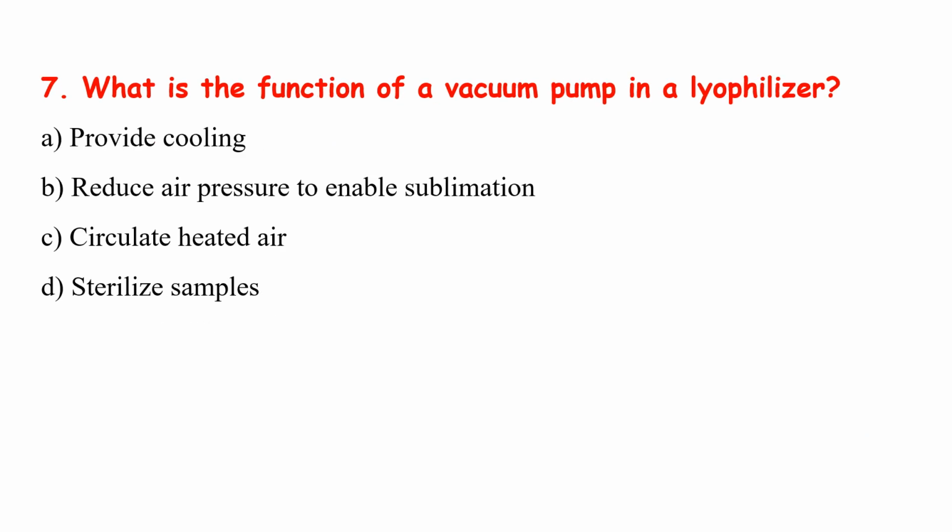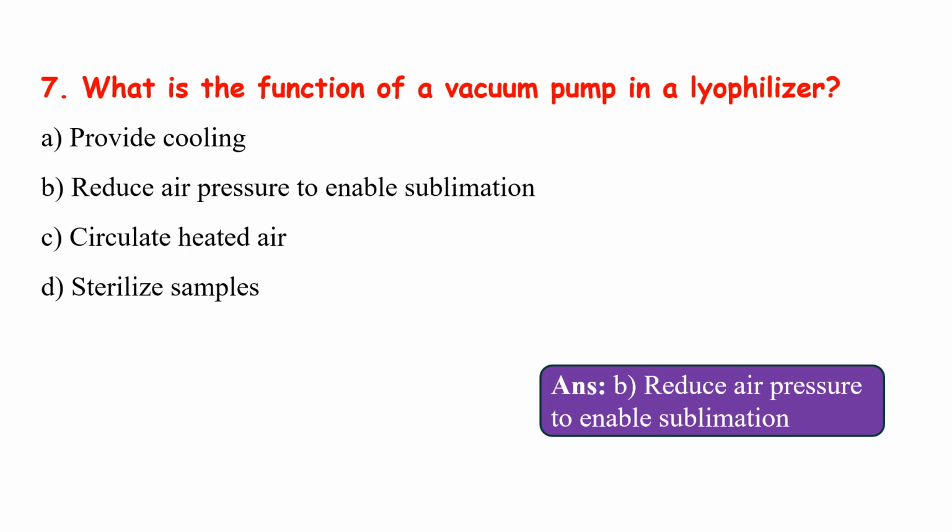What is the function of a vacuum pump in a lyophilizer? Provide cooling, reduce air pressure to enable sublimation, circulate heated air, sterilize samples. The correct answer, reduce air pressure to enable sublimation.